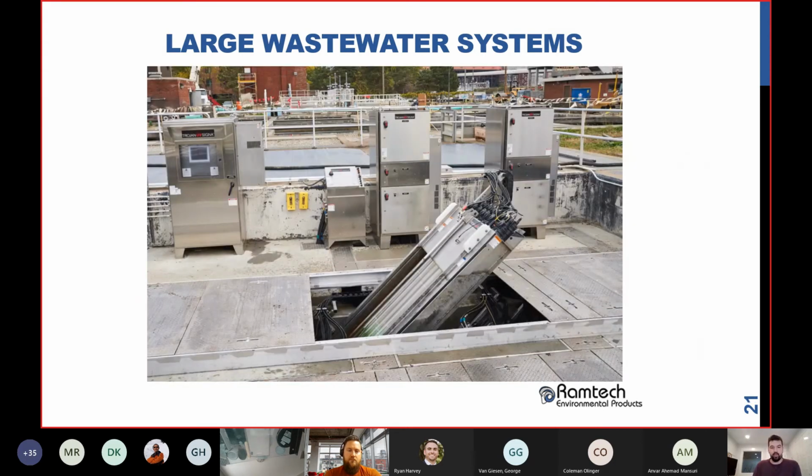This is taken out, so any sleeve or lamp changes you need to make can be done right there at chest level. You don't need to go in and pull a module out. It's much simpler. This is the bank itself. There are your power distribution centers and your hydraulic control system. This is also driven hydraulically and raised and lowered hydraulically. And there's your controller.